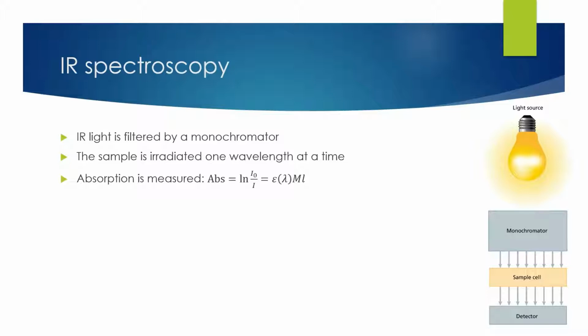I'll go into a little bit more detail about these instruments. The monochromators being limited to one wavelength is not as accurate as you want. So most instruments have these settings, and we'll play with some of these in the future, called slit widths, and they determine how much light can actually get through because it's pretty hard to filter light by one wavelength. So for example, sometimes you might have a slit width of 2 nanometers, and that's going to allow your wavelength of light plus or minus 2 nanometers to get through to the sample.